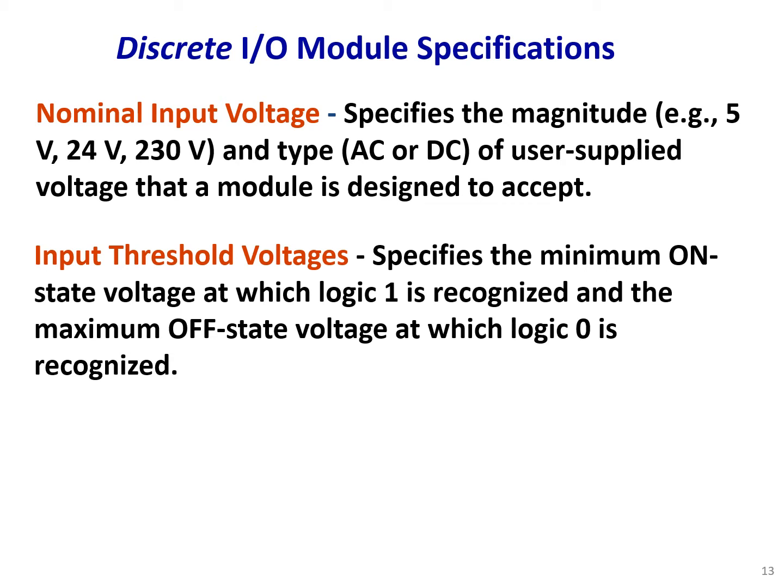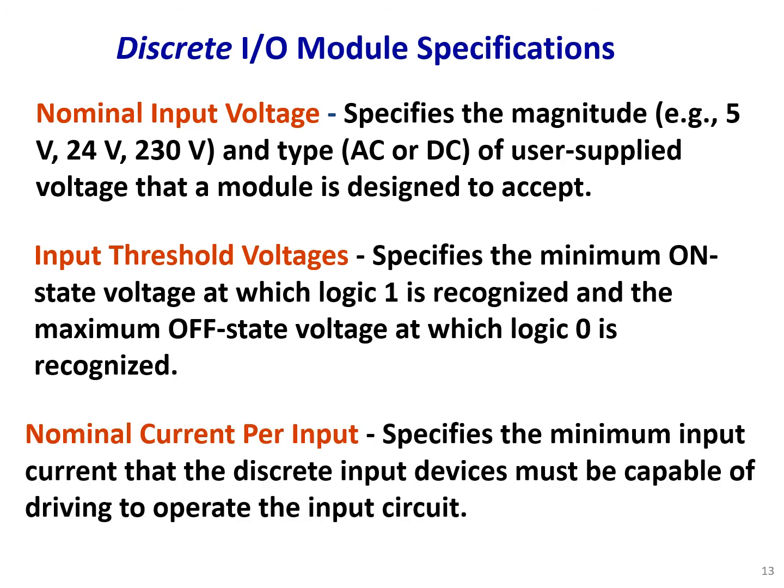Input threshold voltage specifies the minimum on-state voltage at which logic 1 is recognized, and the maximum off-state voltage at which logic 0 is recognized — a range or threshold to translate the input voltage to digital states on or off. Nominal current per input specifies the minimum input current that the discrete input device must be capable of driving to operate the input circuit — basically how much current it draws.